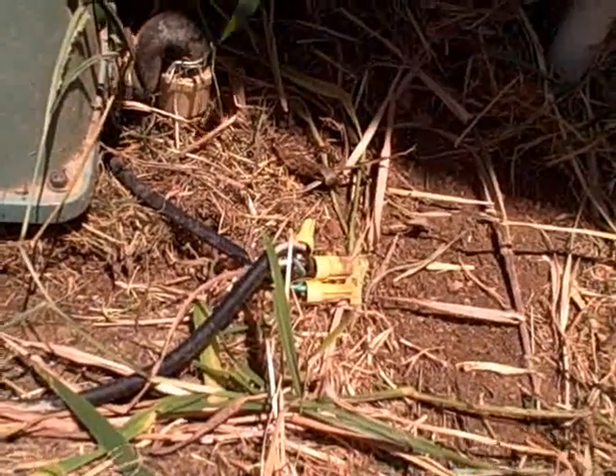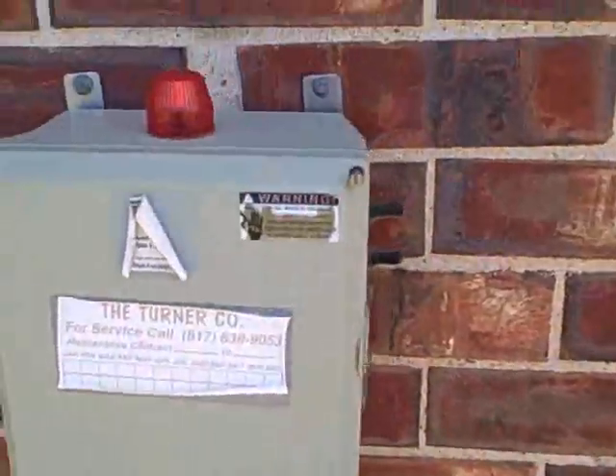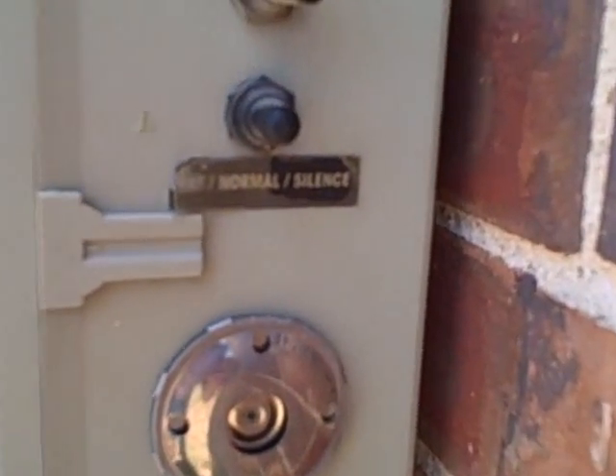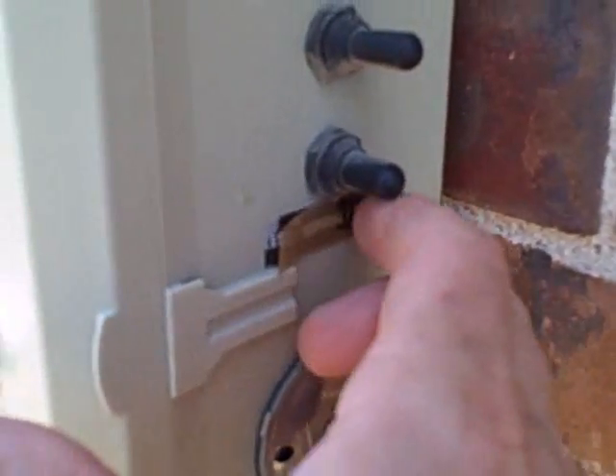You can see here that there are some spliced wires that need to be properly enclosed. As we go up to the control box, one of the first things we want to look at is to see if it's on silent or normal, and then we also want to test the siren while we do this as well.